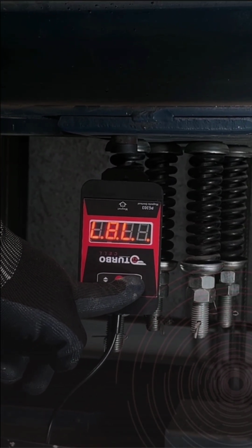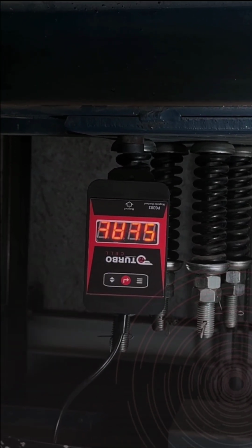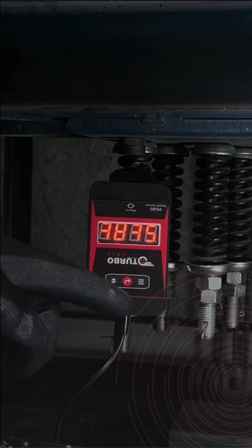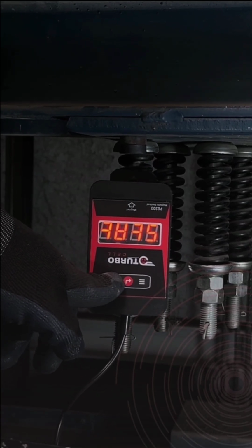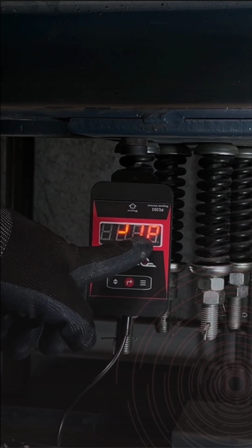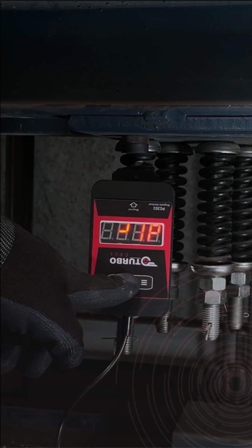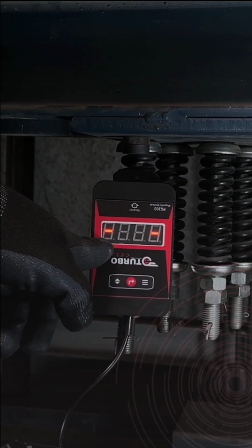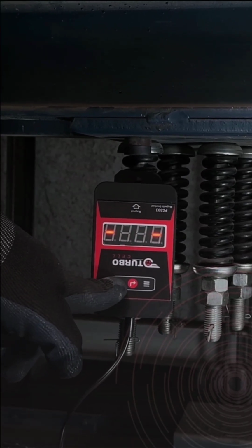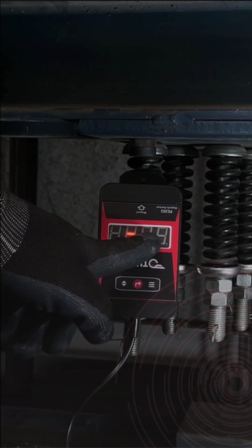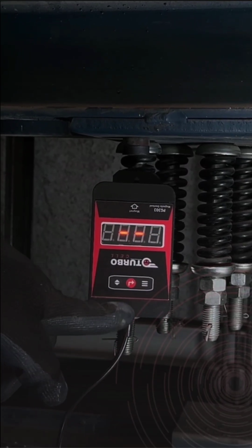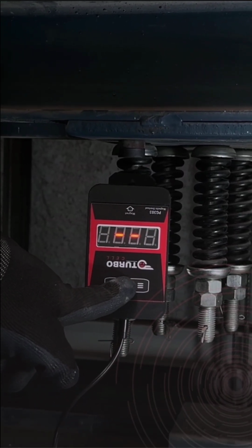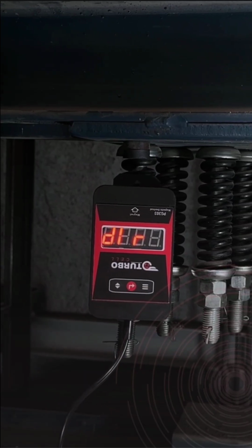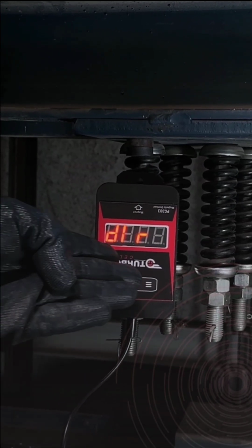Press the UP key once. The parameter DIR will appear, but in inverted form. Enter the DIR menu, then use the UP key to align the 2 central points on the display. This adjustment will invert both the device operation logic and the display orientation. When the correction is complete, the word DIR will appear in its normal orientation.